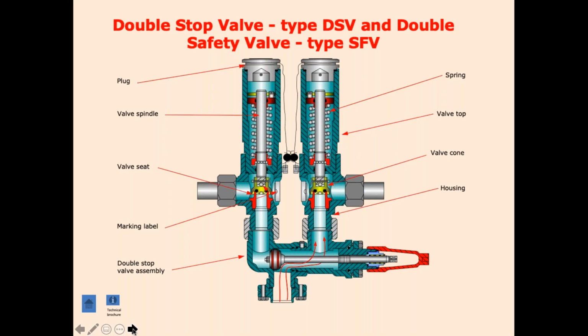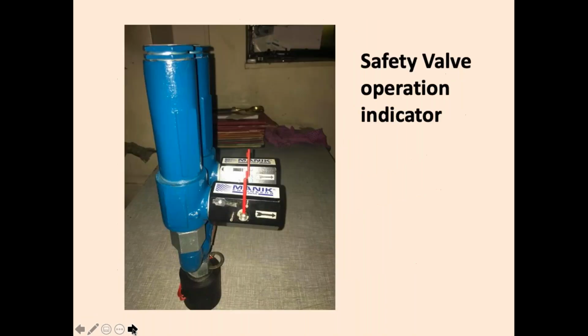How does the dual safety valve function? You can see the stem. The one valve which is on the right hand side is in operation. The stem has closed the left valve. Suppose this valve blows off because of the high pressure, then you can take the stem back. This valve which has operated will close and the second valve will come into operation. So you don't have to remove ammonia from your system. You can continue to operate the plant without any interruption if you use dual safety valves.